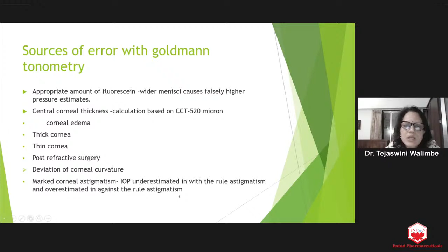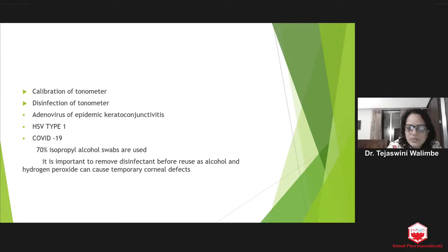Every month, we have to calibrate the tonometer, and the instructions on how to calibrate are given with the machine. Disinfection of the tonometer is very important. Goldmann tonometry measurement can spread the adenovirus of epidemic keratoconjunctivitis through the tear film, then HSV, COVID-19 or HIV, hepatitis virus also. So it's better to disinfect the biprism with 70% isopropyl alcohol swabs. These swabs are commercially available, and it is important to remove the disinfectant before reuse, as alcohol and hydrogen peroxide can cause temporary corneal defects. And the biprism should be dry before reusing.